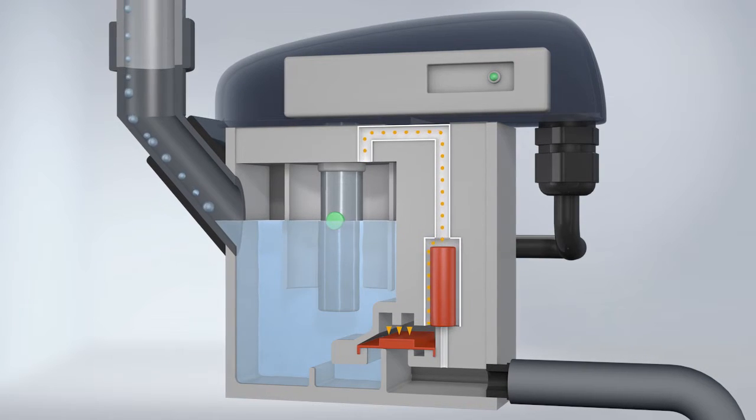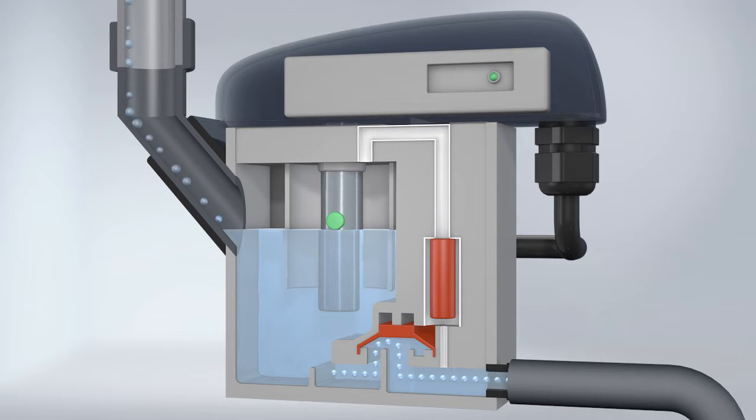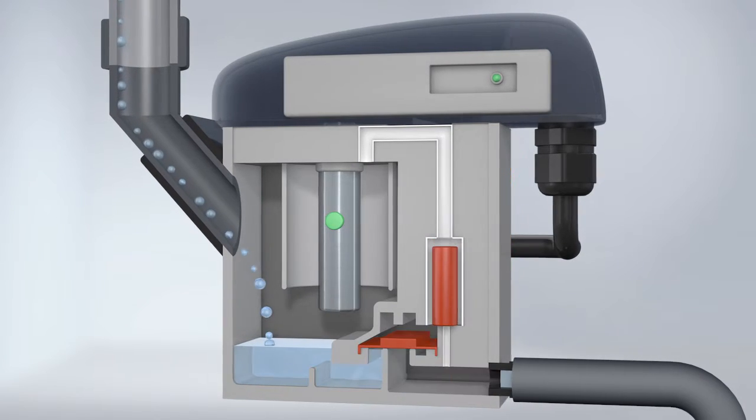When the zero-loss drain is full, the solenoid valve is activated and the space above the membrane is vented. Simultaneously, the pressure on the underside increases, allowing the condensate to flow into the outlet line.